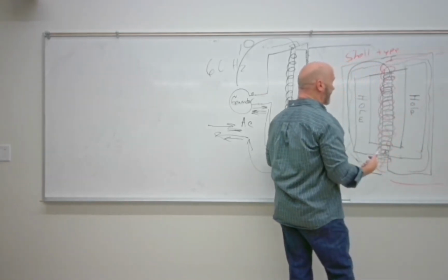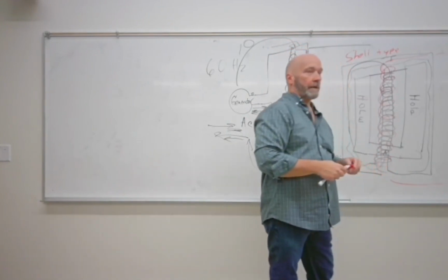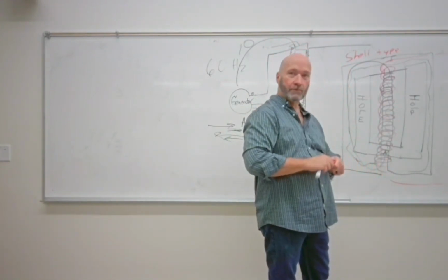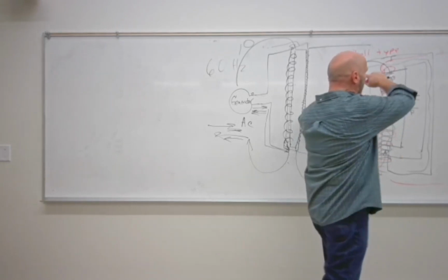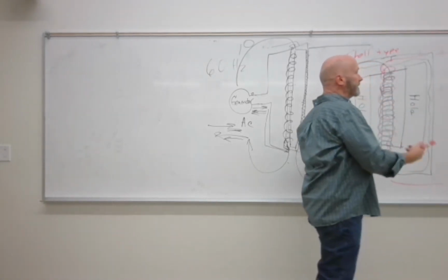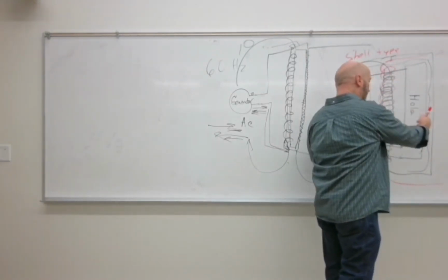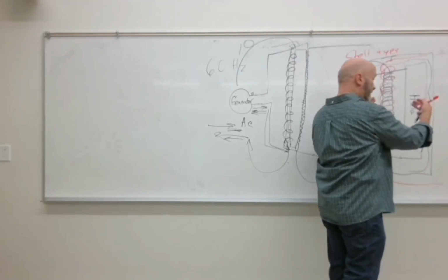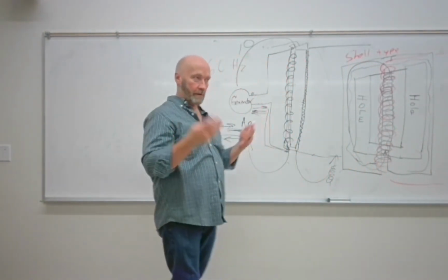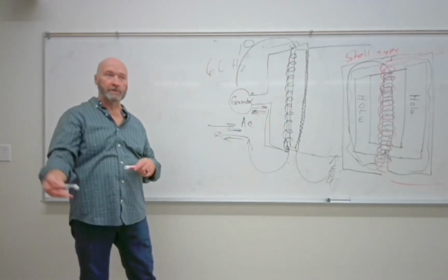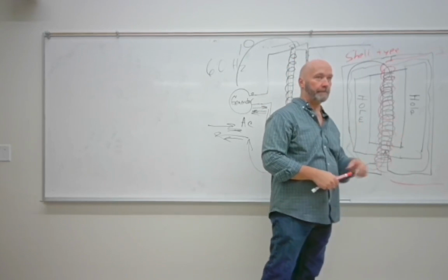So we take all those magnetic field lines and we're jamming them right back up through the center of this thing. We wrap it with a secondary coil of wire with many more turns. Where's the magnetic field going? Back to itself, straight through that secondary coil. So in a shell type, we're giving the magnetic field lines more of a, it's not really 360 degree, but it's at least redirecting those magnetic field lines as much as it can straight back up through the center of both of the coils of wire. And so you increase the efficiency, reduce the loss. Most efficient type of transformer: shell type.